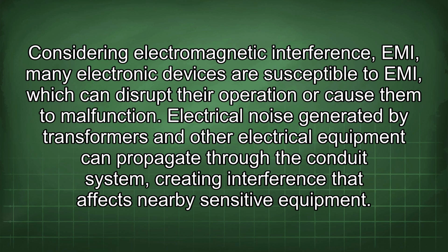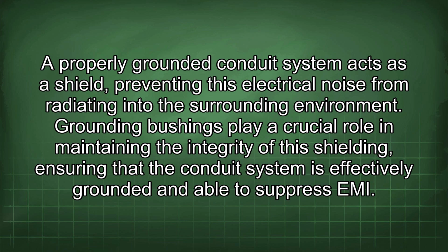Considering electromagnetic interference, many electronic devices are susceptible to EMI, which can disrupt their operation or cause them to malfunction. Electrical noise generated by transformers and other electrical equipment can propagate through the conduit system, creating interference that affects nearby sensitive equipment. A properly grounded conduit system acts as a shield, preventing this electrical noise from radiating into the surrounding environment. Grounding bushings play a crucial role in maintaining the integrity of the shielding, ensuring that the conduit system is effectively grounded and able to suppress EMI.